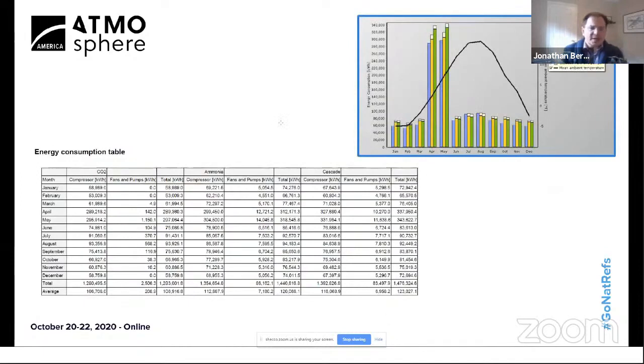Here we have some energy consumption forecasts for three different options: CO2, ammonia, and a cascade solution, which is a CO2 ammonia cascade. The CO2 transcritical package is two-stage, the ammonia system is single stage with economizer, and the cascade system is single stage on each refrigerant.